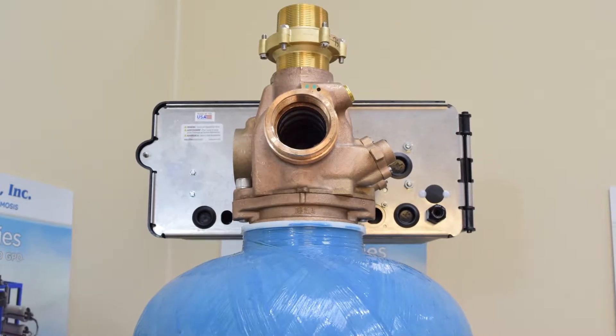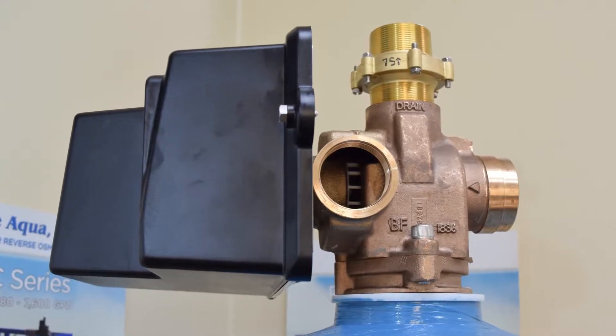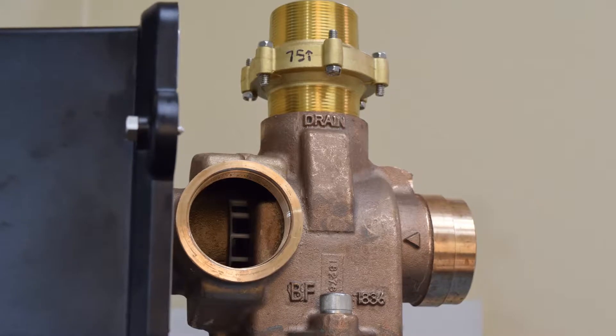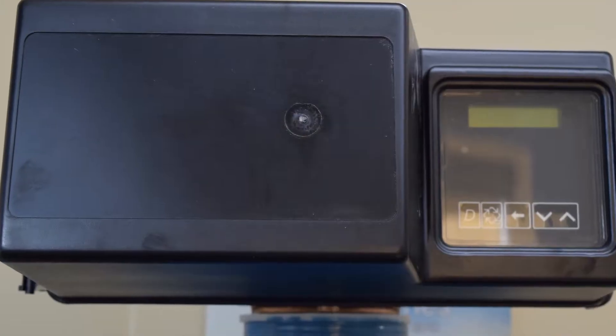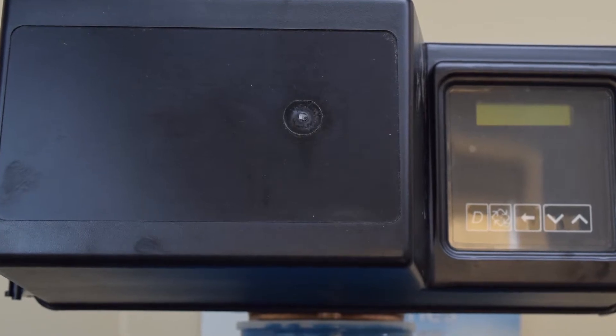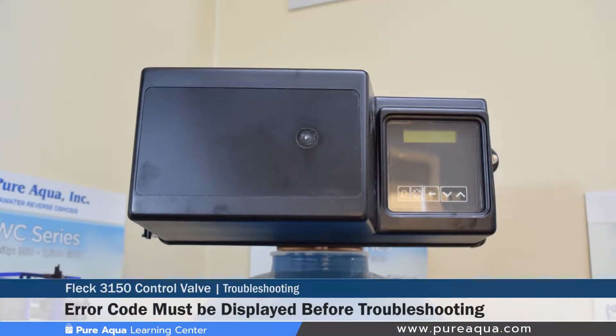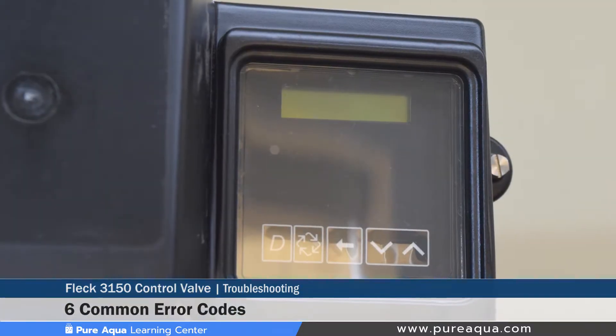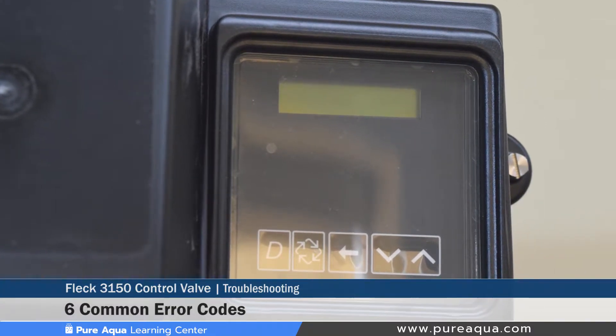In this section of the video, we will cover some troubleshooting and diagnostic steps for the Fleck 3150 control valve. We will discuss the error type, the cause, and some diagnostic steps. It can take the valve up to 30 seconds to detect or display an error, and all errors on each unit in the system must be displayed before the errors can be corrected. Six of the most common errors found on the Fleck 3200 NXT controller will be discussed.